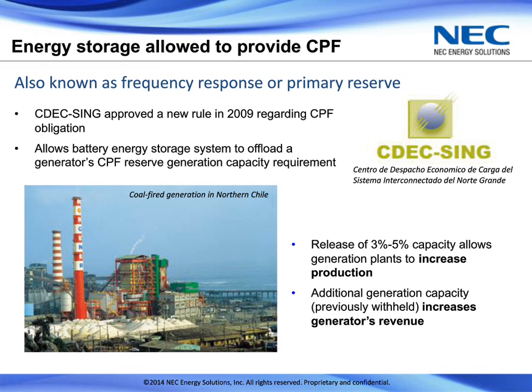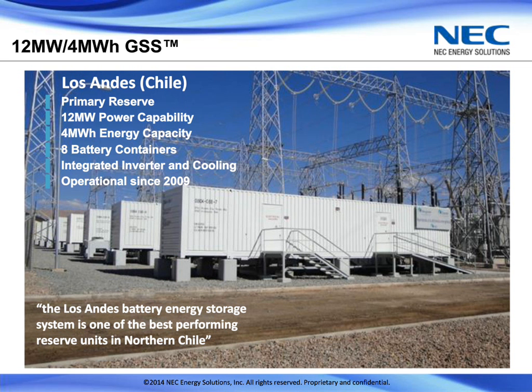So with that new rule in place, allowing battery energy storage systems to take on the obligation for a generator, we then installed a 12 megawatt GSS, which is what we call our grid storage solution, grid scale energy storage products, in Northern Chile. The first system that we installed was put in place in 2009, 12 megawatts of power, 4 megawatt hours of energy, across 8 battery containers. It has been operational since 2009. It has been recognized as one of the best performing reserve units in Northern Chile.